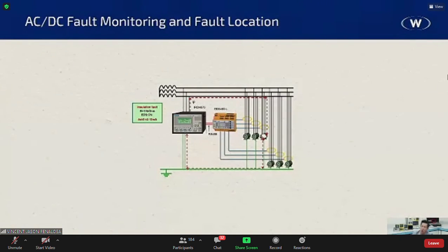Now, once that pulse has been deployed, whichever CT actually senses that pulse kind of tells you which circuit that is. It tells you the address of that device. In this case, the yellow box is address number 2. The channel on that device, I think this is channel 3. And then the actual residual current that was measured, which is about 13 milliamps, giving you an exact location of the circuit where you can check. So that is fault location right there.